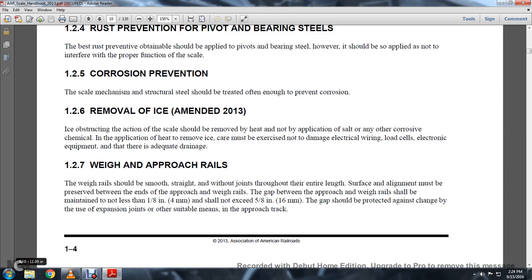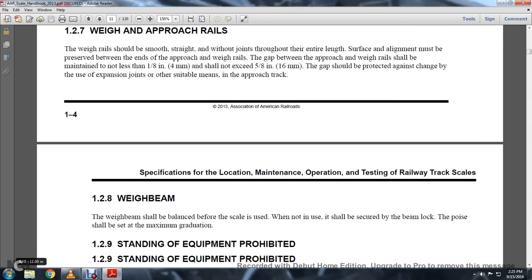1-2-7: Weighing and Approaching Rails. The weigh rails should be smooth, straight, and without joints throughout the entire length. Surface alignment must be preserved between the ends of the approach and the weighing rails. The gap between the approach and the weigh rails shall be maintained not less than 1/8 of an inch (4 mm) and should not exceed 5/8 of an inch (16 mm). The gap should be protected against change by using expansion joints and other suitable means in the approach track.